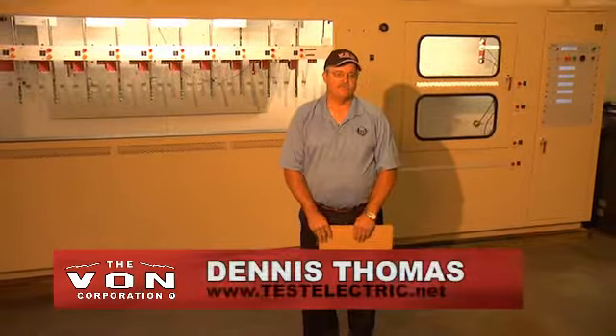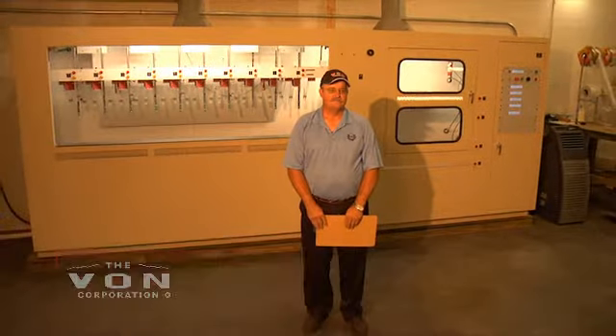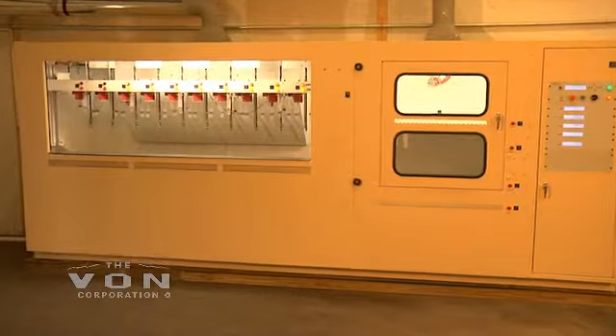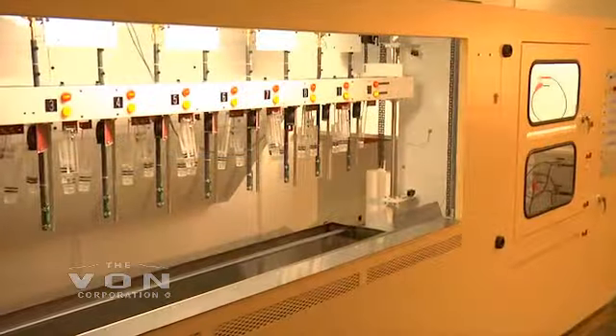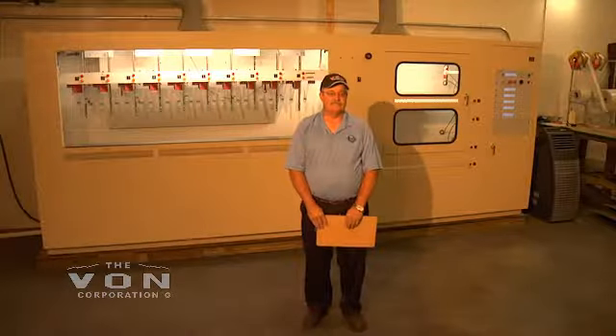My name is Dennis Thomas. I'd like to take a few minutes today to show you the VON Corporation's combination rubber glove, sleeve, line hose, rubber blanket, temporary line jumper, and hood testing unit. It can range from 0 to 50,000 volts AC or 0 to 80,000 volts DC.